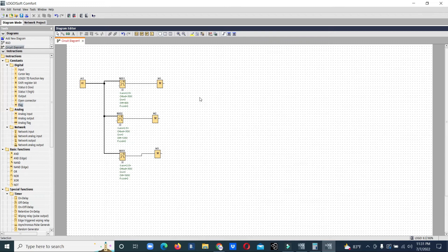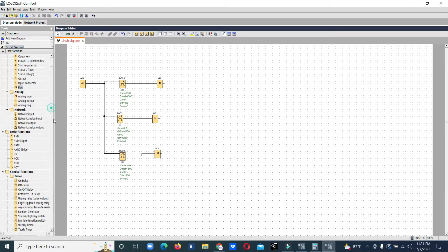But one pump will keep running for a long time, so we need to implement cyclic logic. What we will do is use timing: in 24 hours, the first 8 hours pumps 1, 2, 3 will be in rotation. The next 8 hours, pumps 2, 3, 1 will rotate. The next 8 hours, pumps 3, 1, 2 will rotate. That means in each cycle, any one pump will be running to maintain the maximum pressure. For this we will use a 24-hour timer.